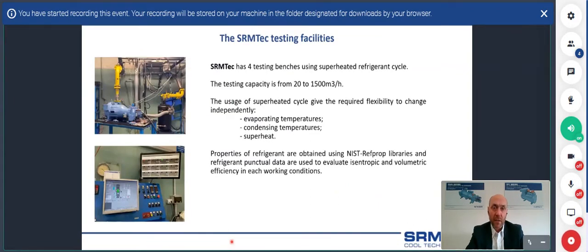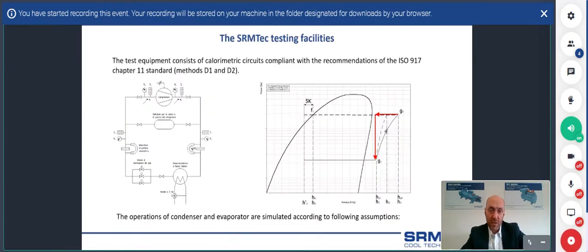In SRMTec, we have full-featured testing facilities. We have 4 testing benches for capacity, especially displacement between 20 and 1,500 cubic meters per hour. And our systems are designed in order to deeply evaluate the behavior of the compressor. So we use superheated cycles in order to be very flexible in the change of the parameters. And just for your information, with this system, we can change independently evaporating temperature, condensing temperature, and also the superheat. This permits us to really map the behavior of the compressor in the very wide application envelope of different conditions.